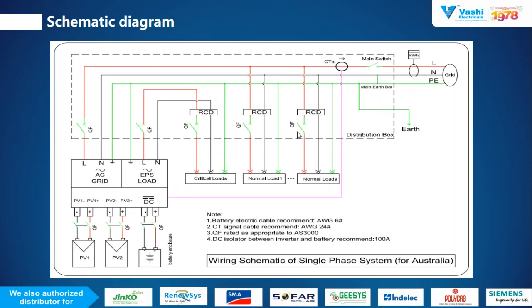Normal load is connected with the grid and CT, according to the CT feedback which is given to the inverter for the regulation of load. If your load is continuously changing, those changes in load current are given by the CT. CT is sensing the load current and gives the feedback to the inverter. You can see the CT connection is before the grid, so it can provide the variation of the load current to the inverter. When the grid is available, the grid supply drives the critical load as well as the normal load.